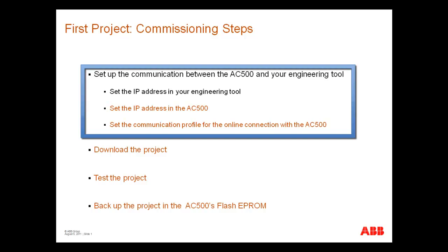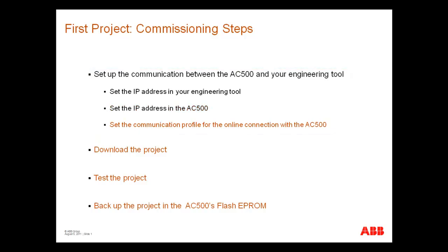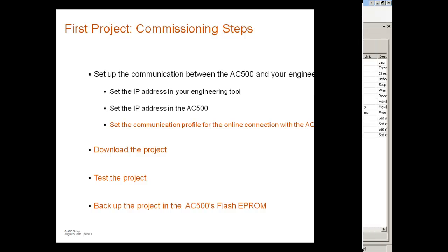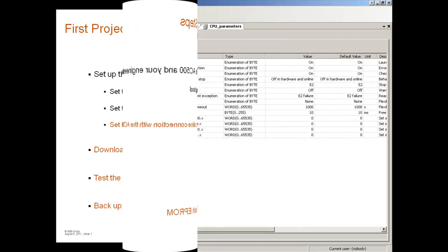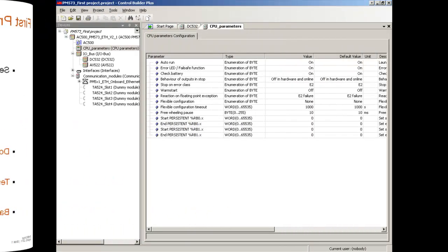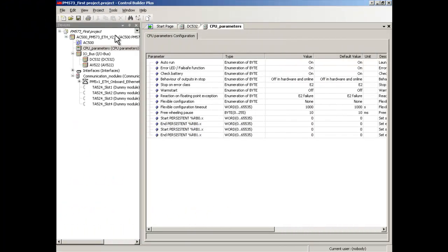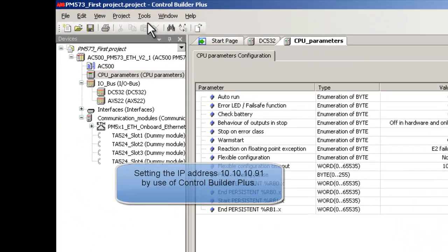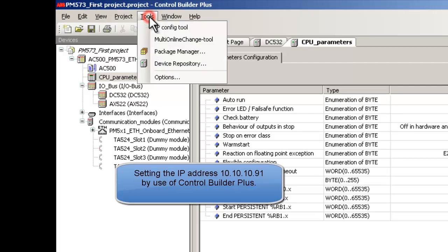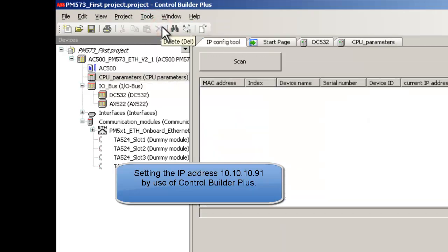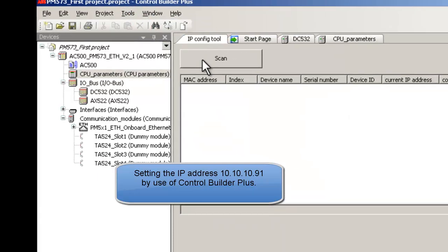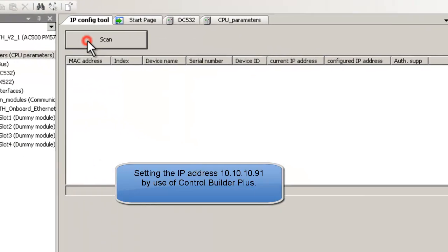Now, we are going to set the IP address in the AC500 controller. In the control builder plus, select the menu tools, and then IP config tools. Then click on the button scan.